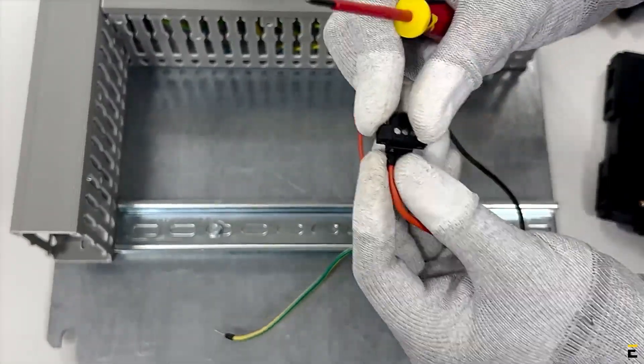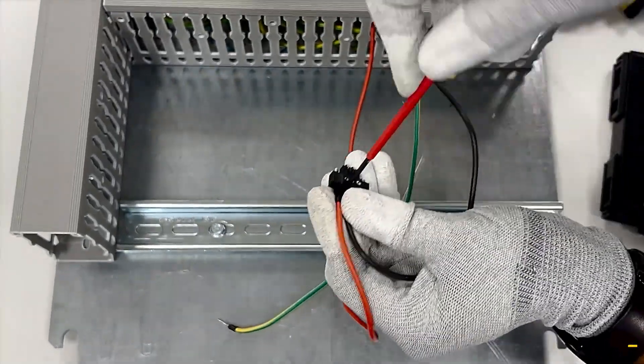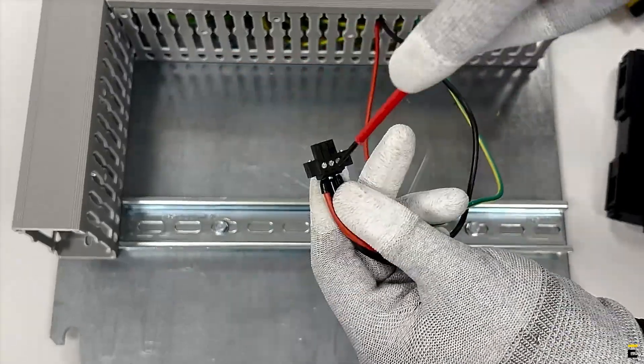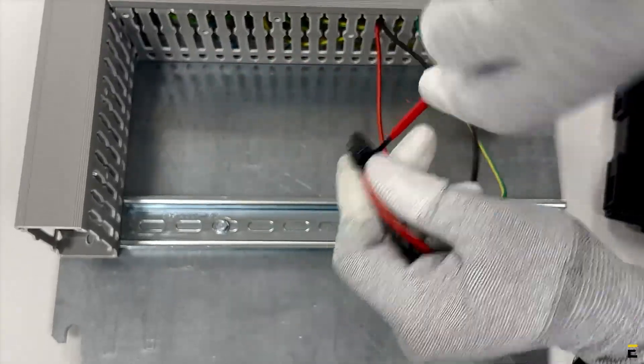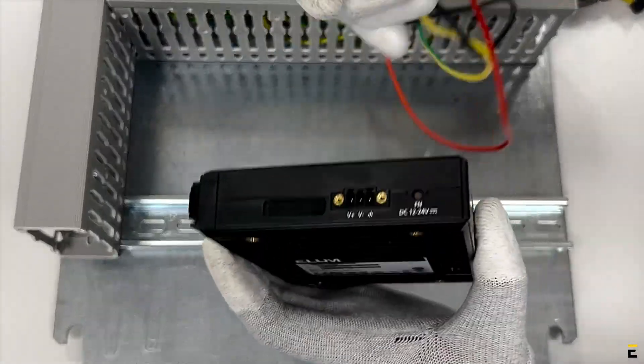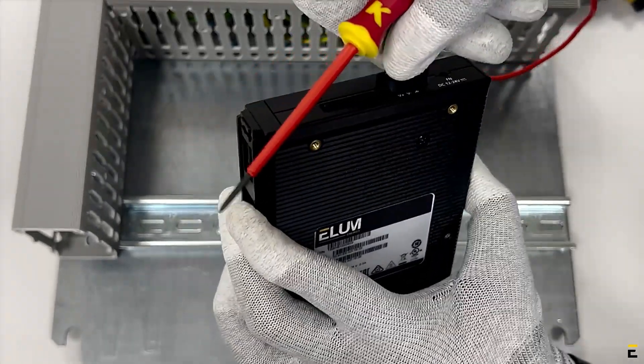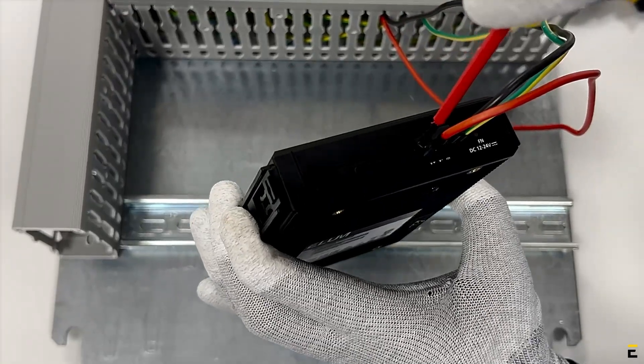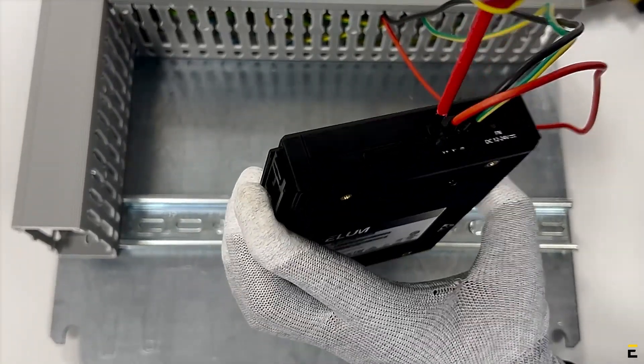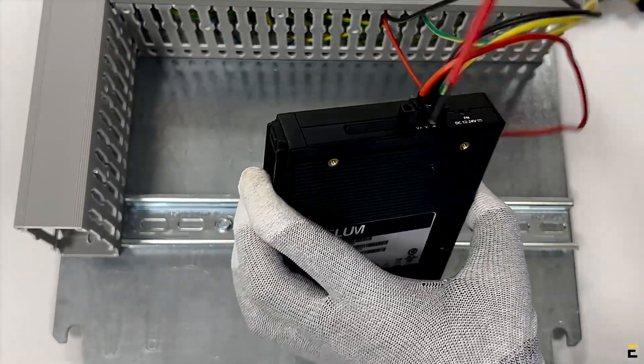Using boot lace ferrules is recommended here. Connect the positive cable (red) to the V positive pin. Connect the negative cable (black) to the V negative pin. Connect the ground cable (yellow-green) to the ground contact. Ensure all cables are securely connected to the power terminal block connector. Reconnect the power terminal block connector to ELUM's device, keeping the ground contact at the top. Use a screwdriver to tighten the screws at the ends and ensure the connector is securely connected and properly tightened.